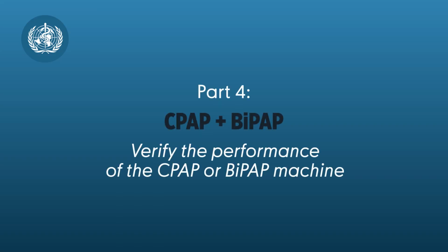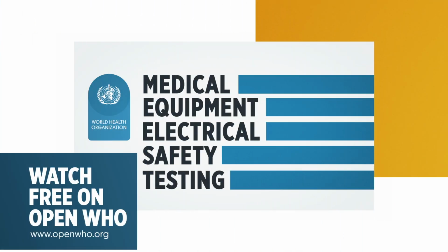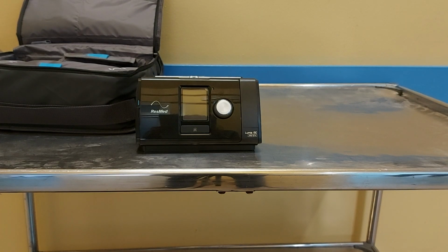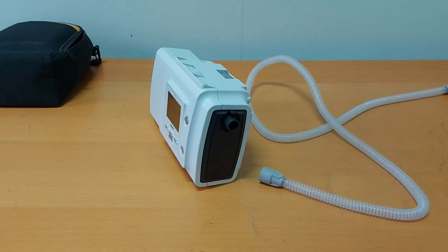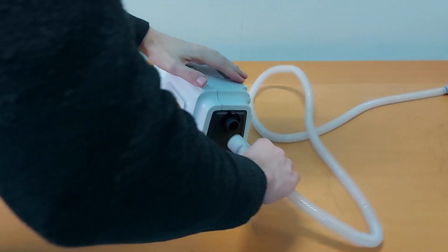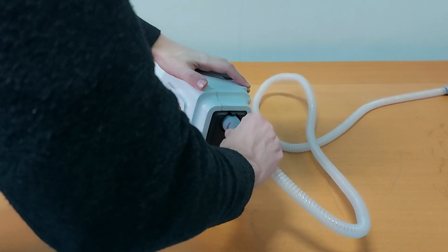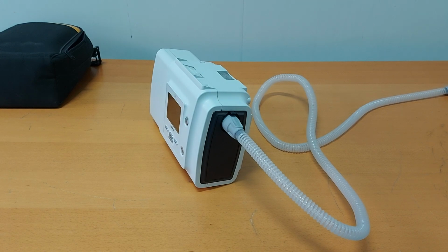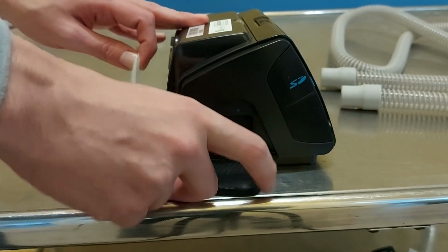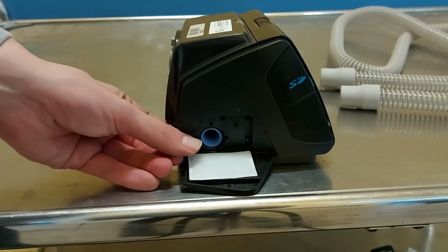Now you are ready to test the performance of the CPAP or BiPAP machine and confirm it is within specifications. Electrical safety testing should be the first performance test. It is covered in a separate video, Electrical Safety Testing. To set up either the CPAP or the BiPAP machine, place the machine on the workbench or table. Keep the device away from any heating or cooling source, as well as any direct sunlight. Connect the tubing onto the device patient outlet port. Remember to never stretch, crush, or deform the tubing to avoid air leaks. Install the air filter if it does not come installed into the device.